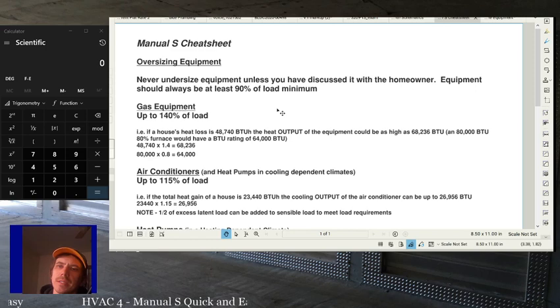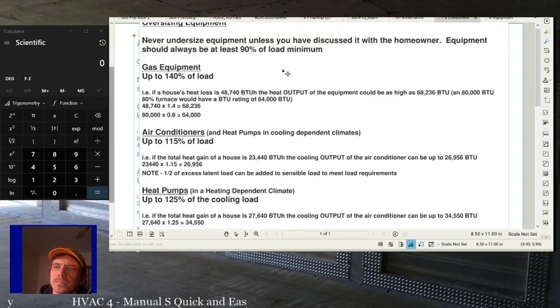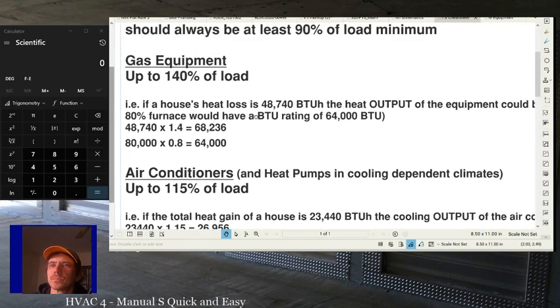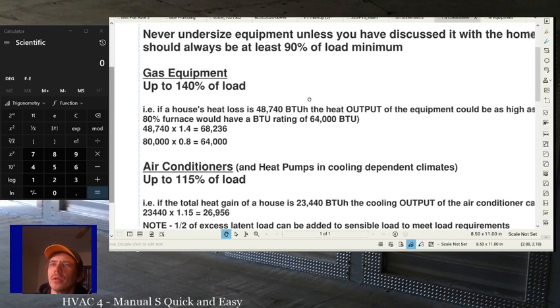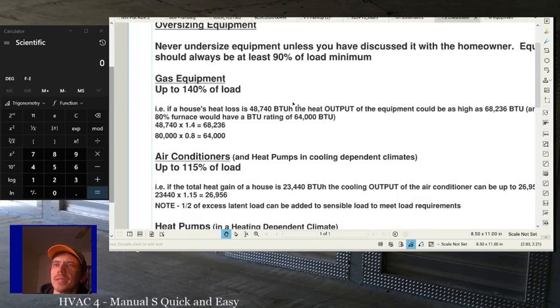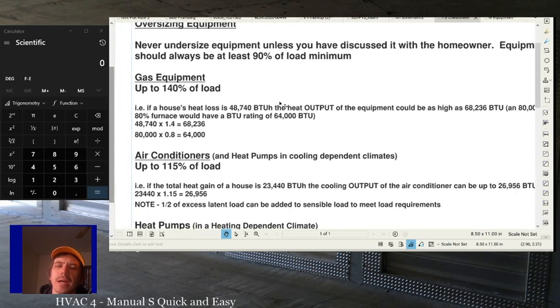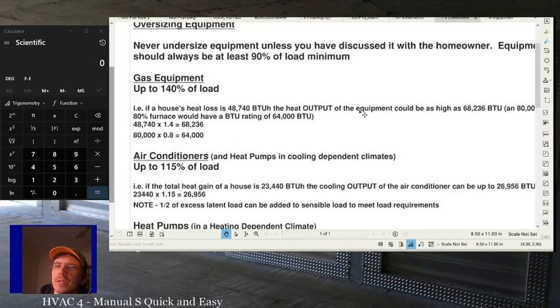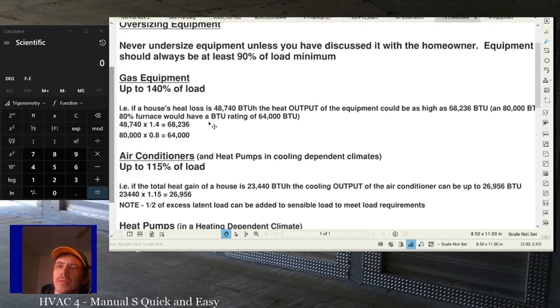Your equipment should be at least 100% of the load, and then you can oversize it based on the type of equipment you're using. So for gas equipment, we can go up to 140% of load, right? So that means that, say, a house's heat loss in the winter is 48,740 BTUs. The heat output of the equipment could be as high as 68,236 BTUs. And an 80,000 BTU 80% furnace would have a BTU rating of 64,000 BTUs.